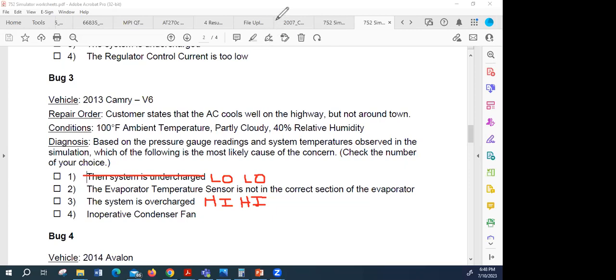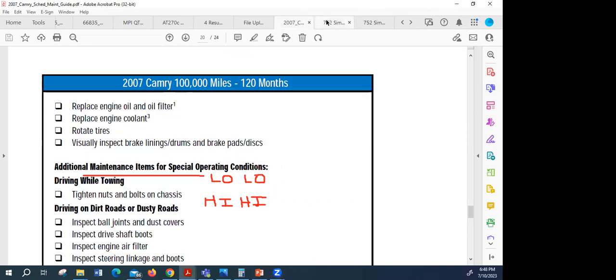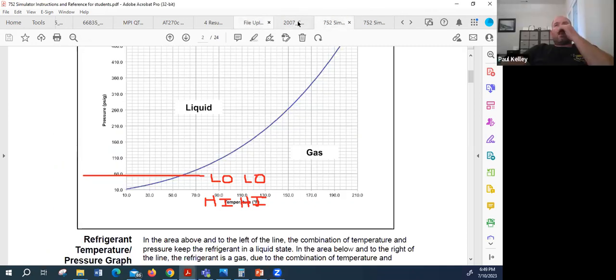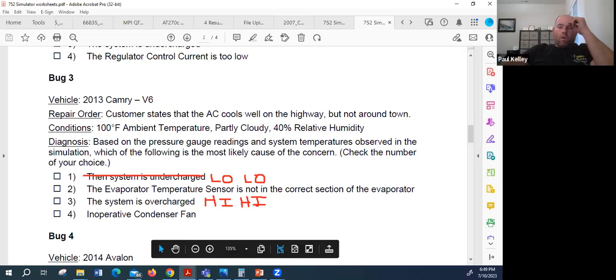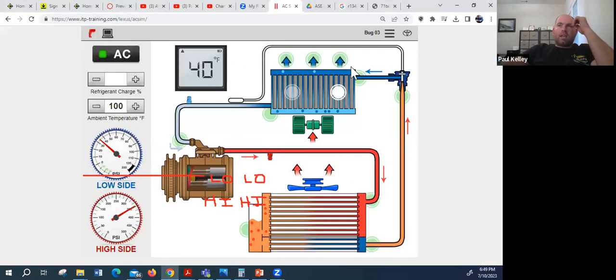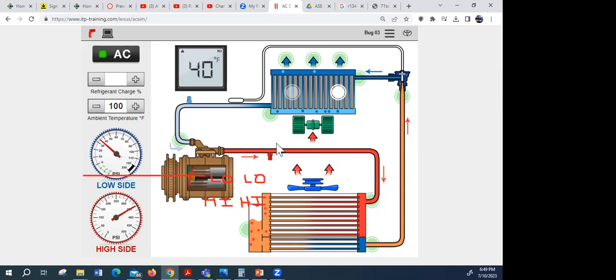And the components would be strained too. If it was overcharged, maybe the compressor would be working too tough. It kind of depends on how much we're talking, so let's say it was way overcharged, and we can't adjust that amount on this one. That high side can only get so high before a sensor actually turns the compressor off. In that case, it self-protects.